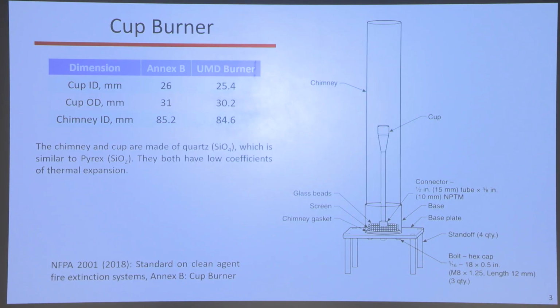This is almost like an oven. The cup gets very hot, and the chimney also can get quite hot. And this is an NFPA standard, actually, from 2018. Okay, so that's the cup burner, and those are the dimensions.